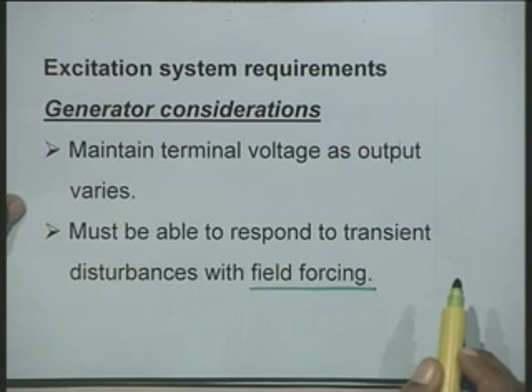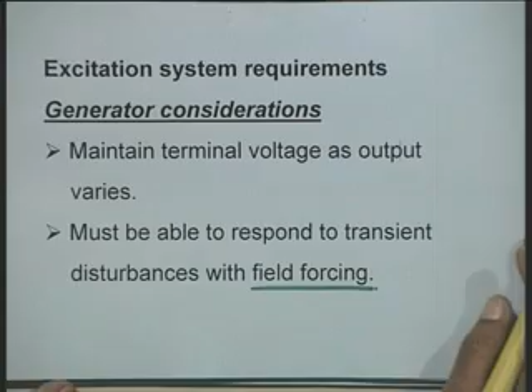Our excitation system should be such that whenever there is some transient disturbance, following that disturbance, you can resort to field forcing. Field forcing means we apply a large voltage to the field winding of the synchronous generator, so that more current can flow through the field winding. That is, excitation current can be increased temporarily, for a short duration. This field forcing capability is one of the important requirements of the excitation system. As we will see, to have good field forcing capacity, the excitation system is designed with a high ceiling voltage.